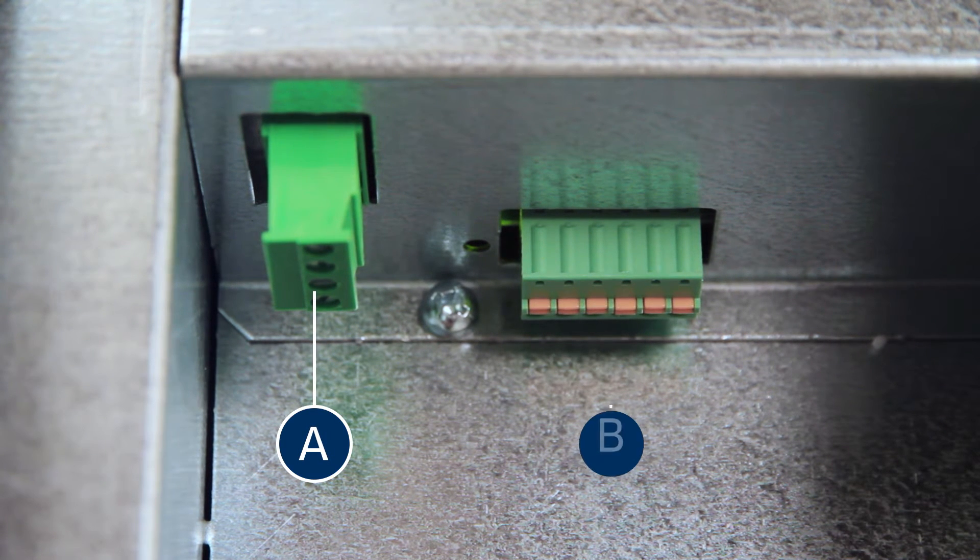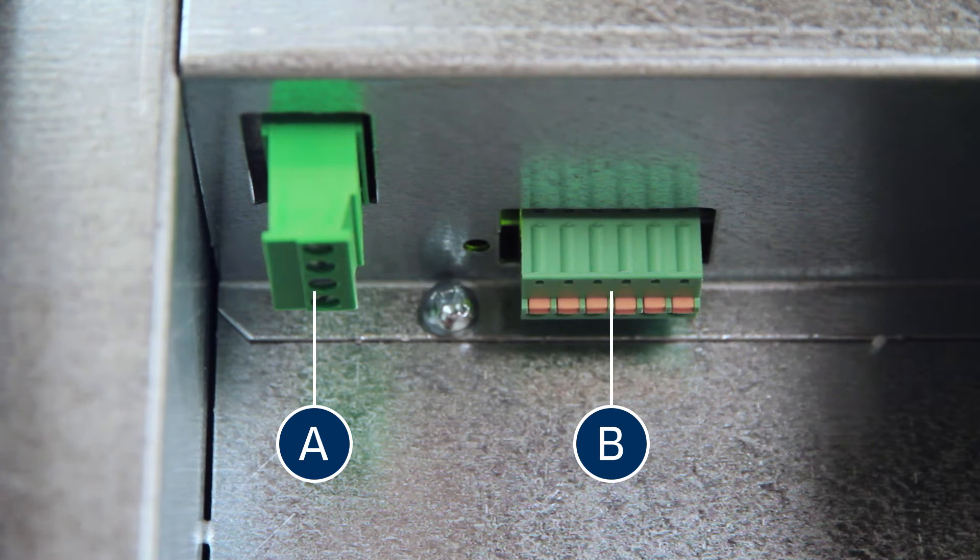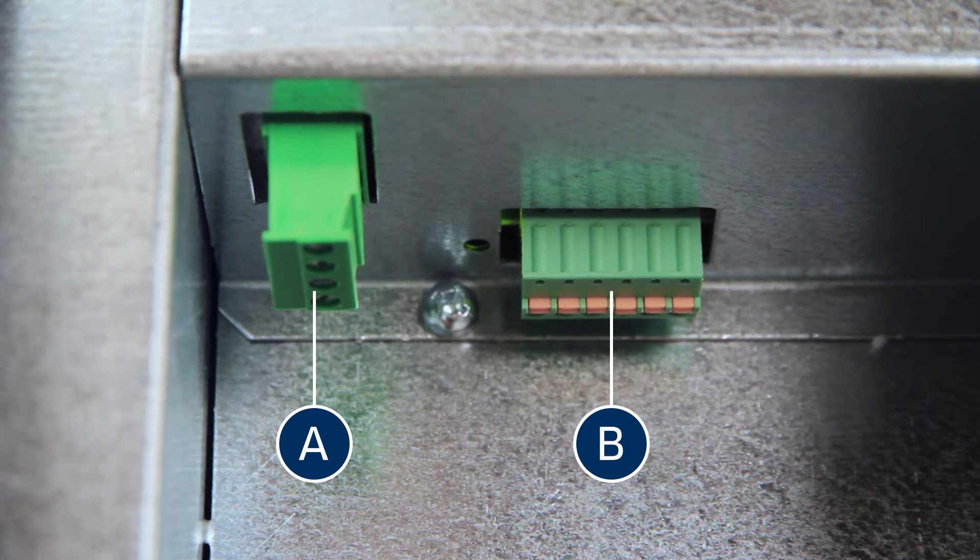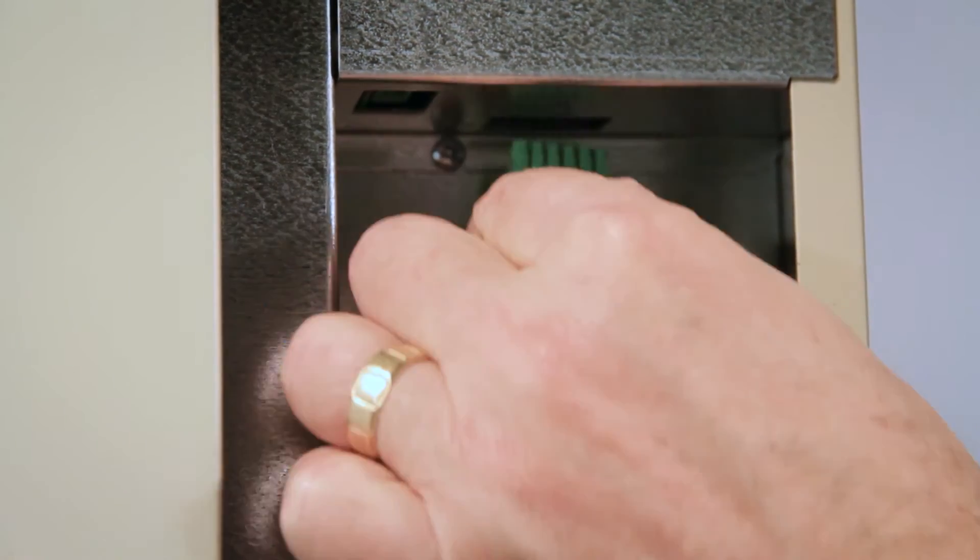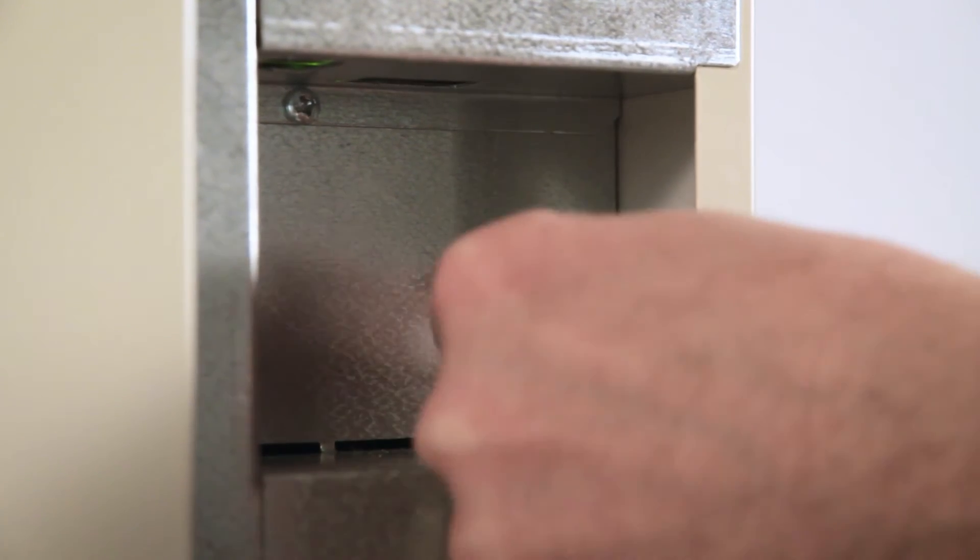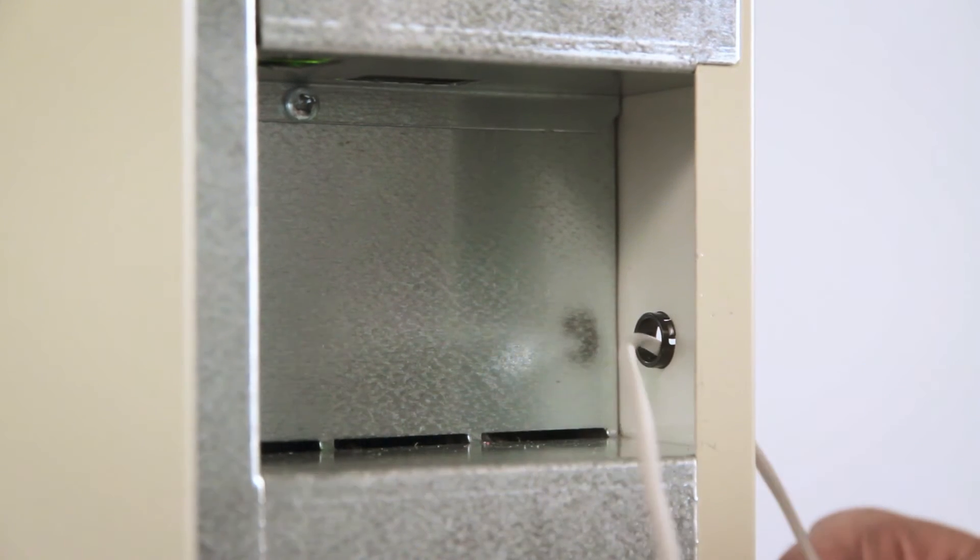A is the one for main control connection only and B is the one for auxiliary control and furnace interlock. Pull the required connectors out from the unit board. Run the end of the control wires through the grommet located on the unit wall as shown.